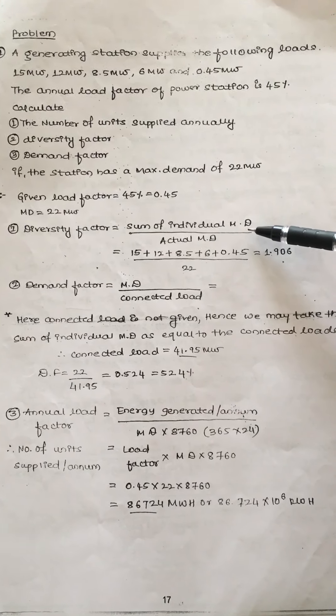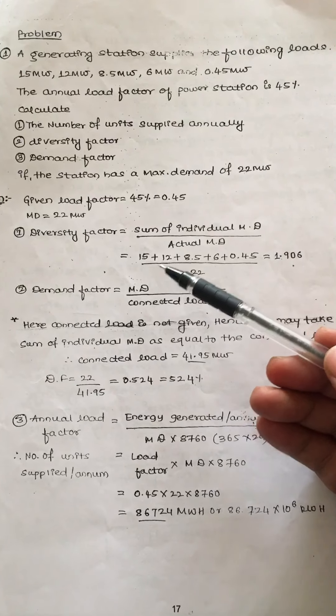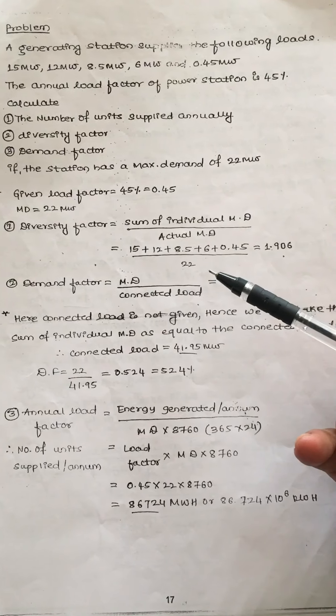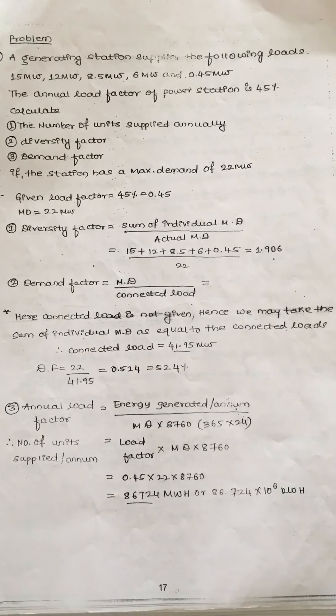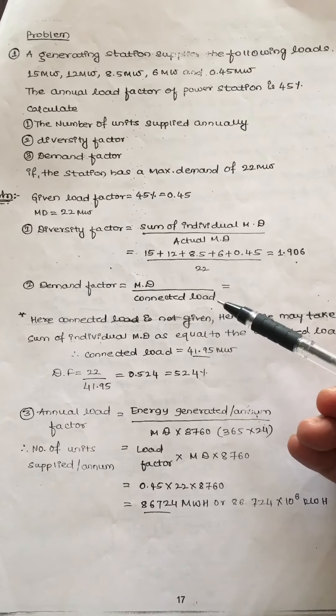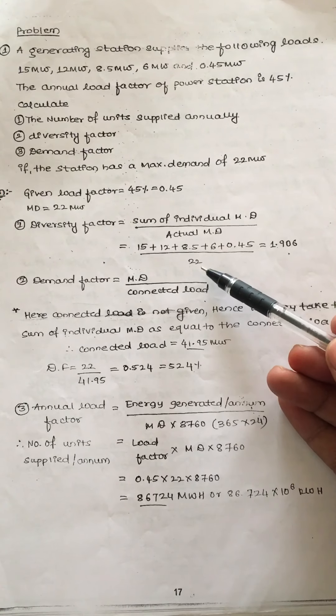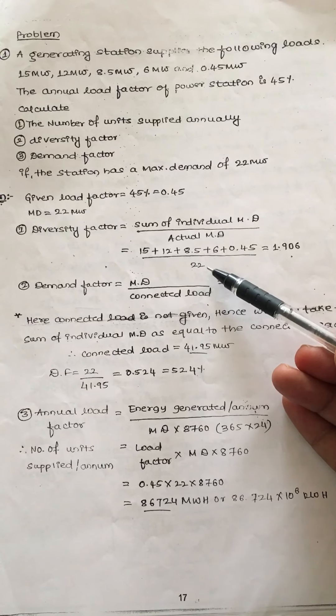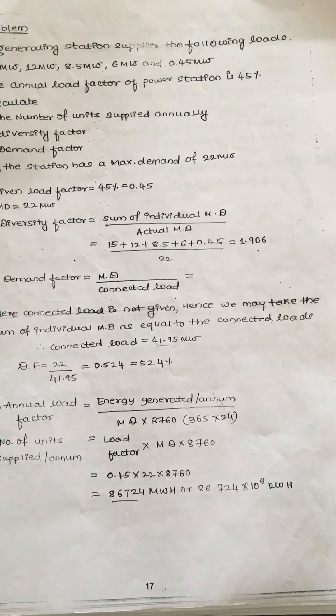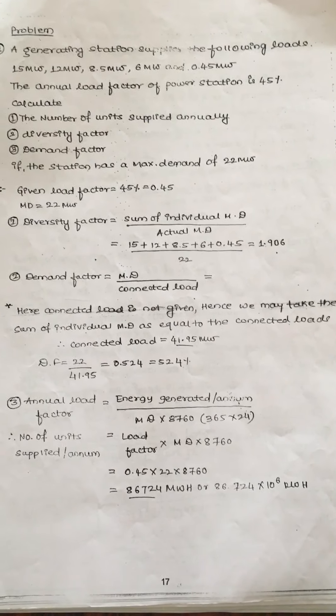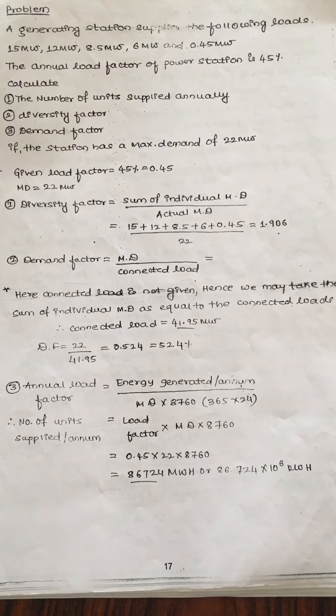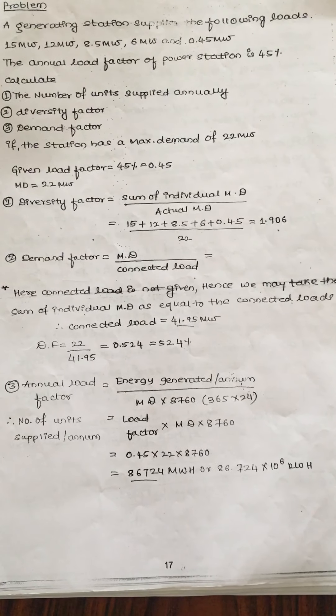The individual maximum demands are 15 megawatt, 12 megawatt, 8.5 megawatt, 6 megawatt, and 0.45 megawatt. The sum of these divided by the actual maximum demand of 22 megawatt gives us 1.906, which is the diversity factor.